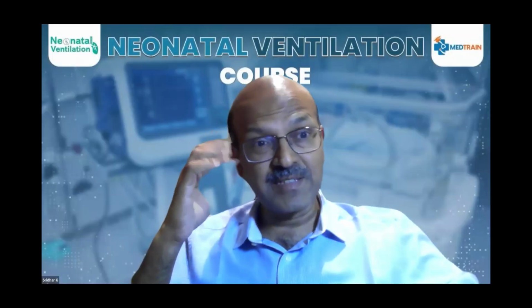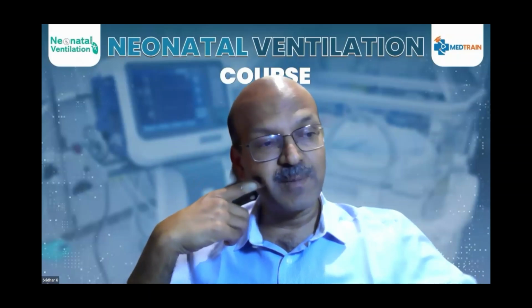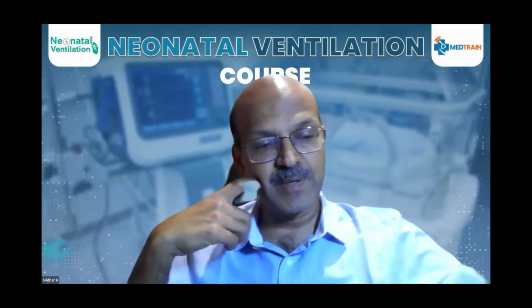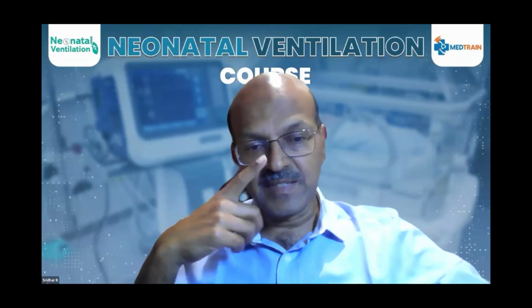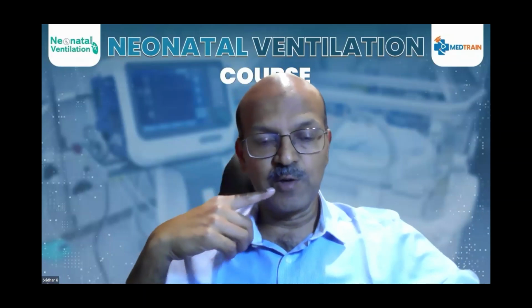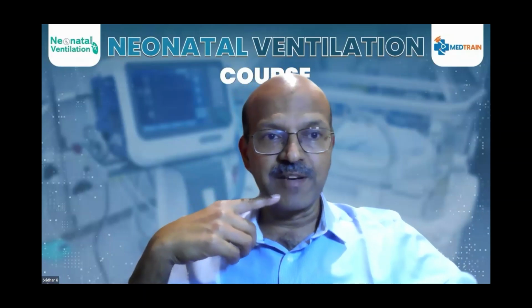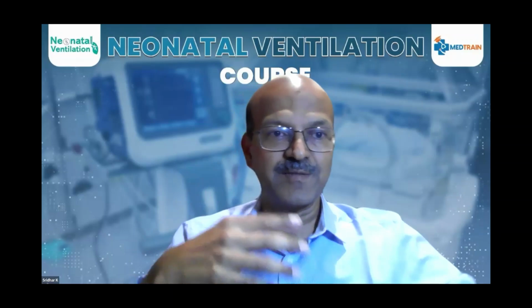What is your experience regarding electrolytes in blood gases? I feel you have to be alert. It depends a lot on calibration and how they are fine-tuning each aspect of it. Even in the same machine, sometimes it fluctuates. So you always have to be alert. And if you have any concerns, we don't treat on the basis of electrolytes on the gas.